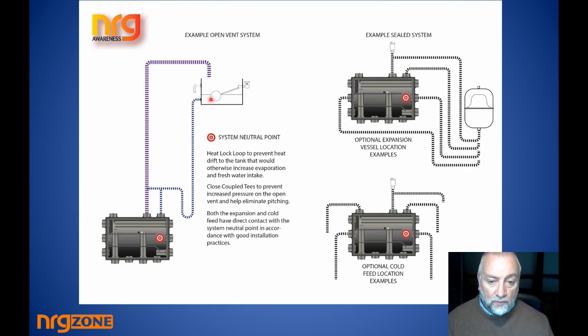If hot water gets into the tank, it starts to form convection currents around the tank, where the hottest water goes to the top, the cold is drawn back, and in a very short period of time your expansion tank is hot. If your expansion tank is hot, what's going to happen is pure common sense. It will evaporate. If it evaporates, fresh water has to come in through the ball valve, and here you have the scenario that everyone wonders: how the hell are all of these systems getting gunked up with rubbish when there's no leaks and where the pumps are not whatever? It's because the cold feed is in the wrong location.